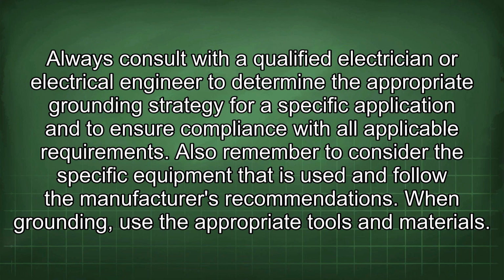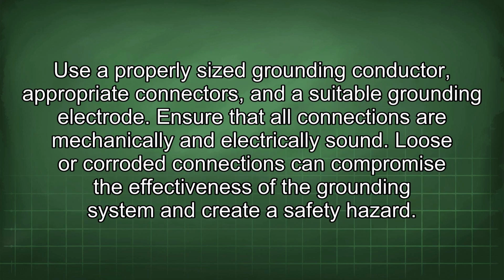Also remember to consider the specific equipment that is used and follow the manufacturer's recommendations. When grounding, use the appropriate tools and materials. Use a properly sized grounding conductor, appropriate connectors, and a suitable grounding electrode. Ensure that all connections are mechanically and electrically sound. Loose or corroded connections can compromise the effectiveness of the grounding system and create a safety hazard.